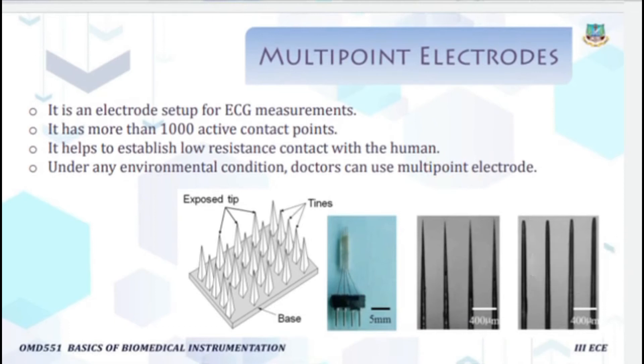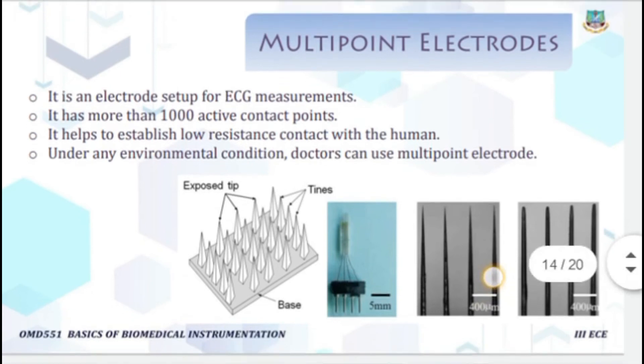The next type is the multi-point electrode, also used for ECG measurement. It has more than a thousand active contact points for generating the signal and establishing low-resistance contact with the human body. This electrode can be used under any environmental condition and is used without removing hair in the area where biopotential is being picked up.